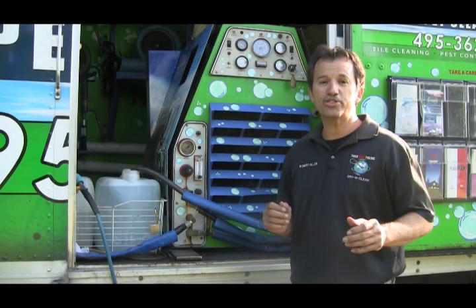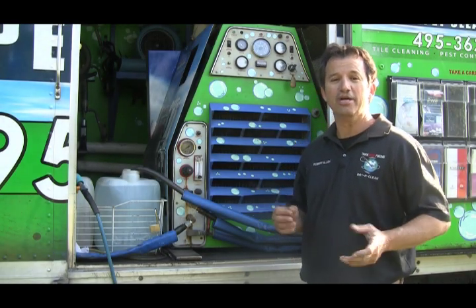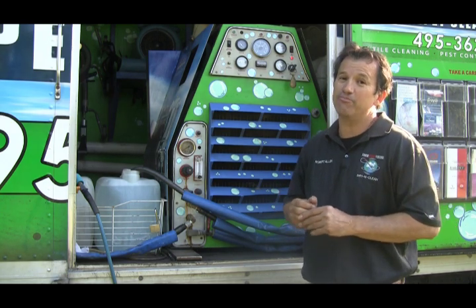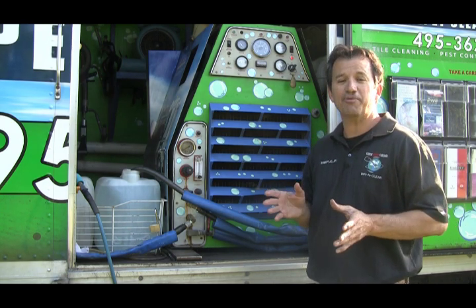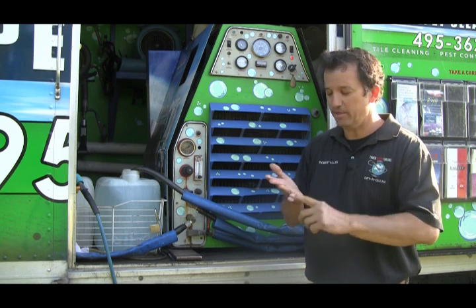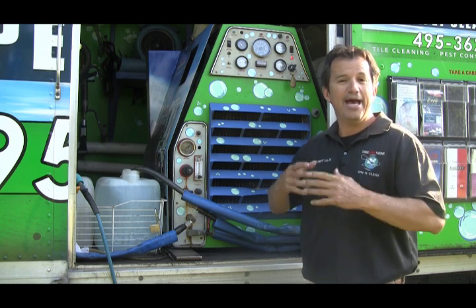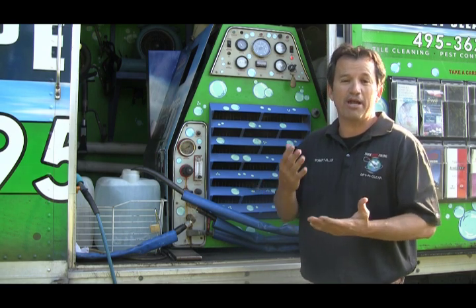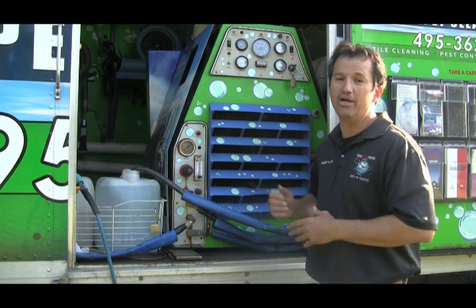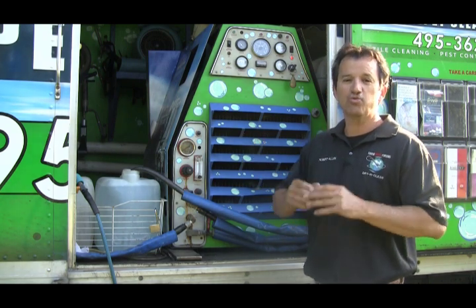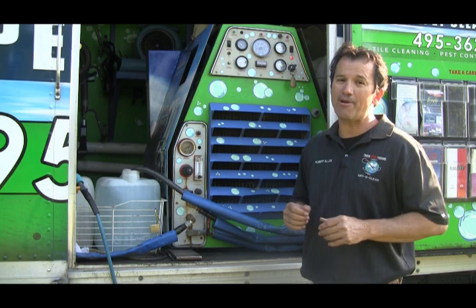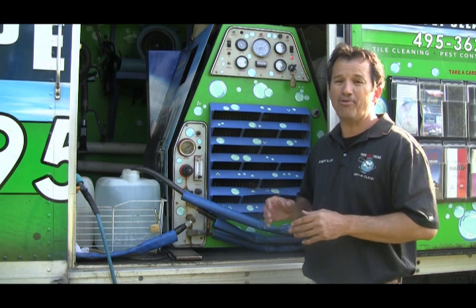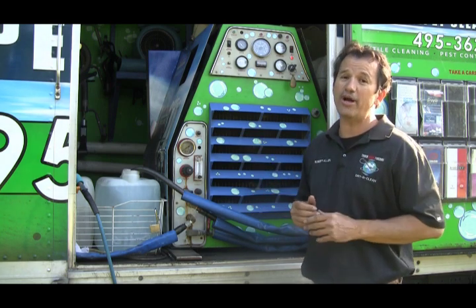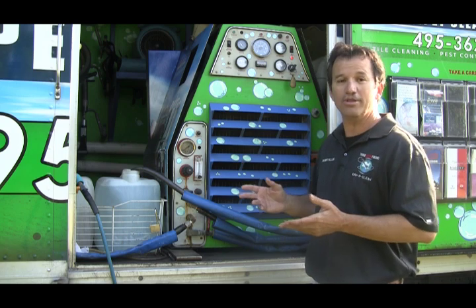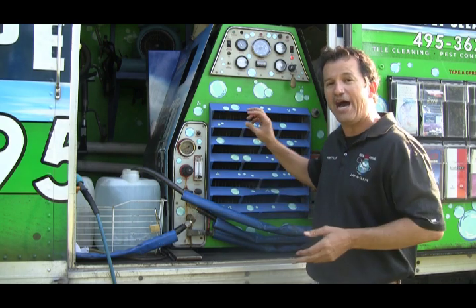Now, heat exchanger technology, like I mentioned earlier, is the one you run into the most problems with, usually. That's because they use exhaust heat from the engine and blower heat, and sometimes have more than one heat exchanger — this unit has 4. So it's really important to take the time to cool it down properly. You don't want all that heat and pressure stuck inside the unit, or it's going to lead to issues.